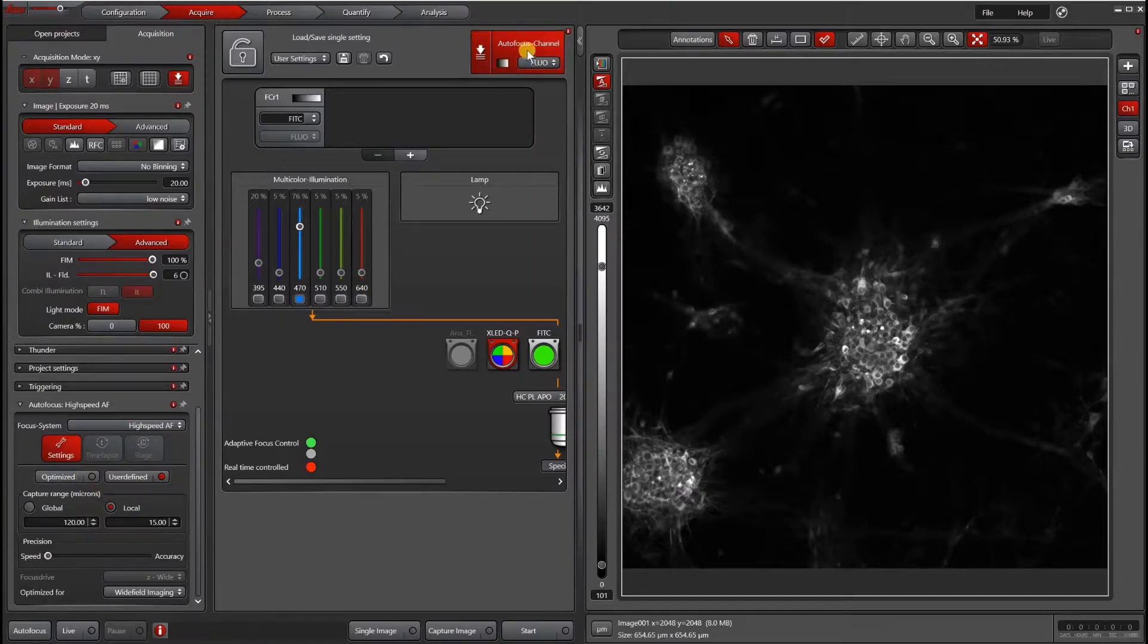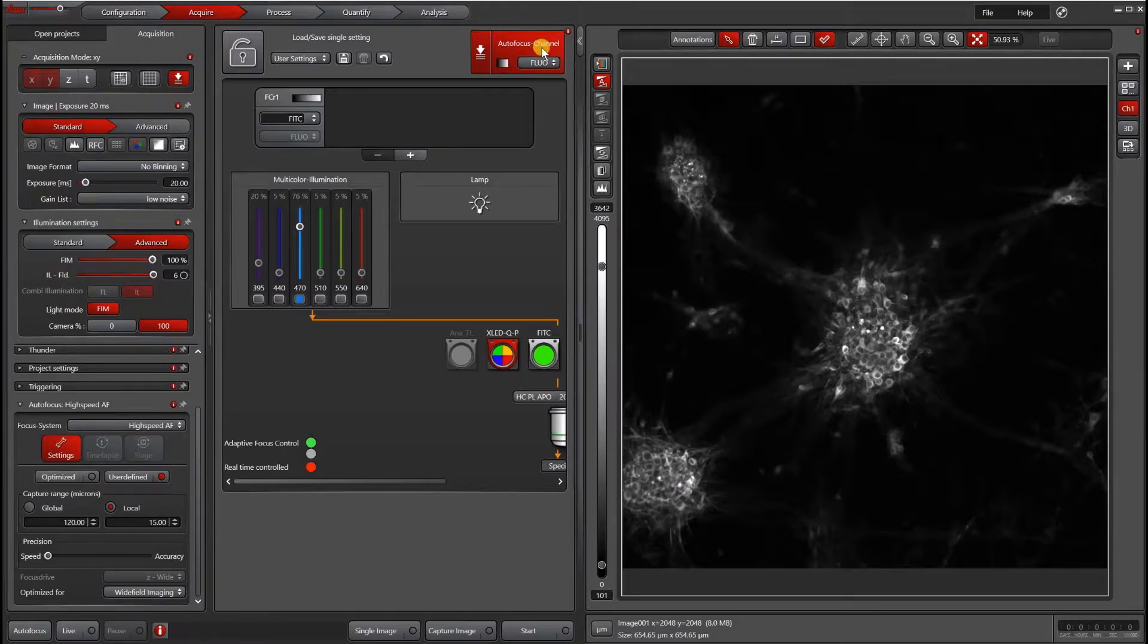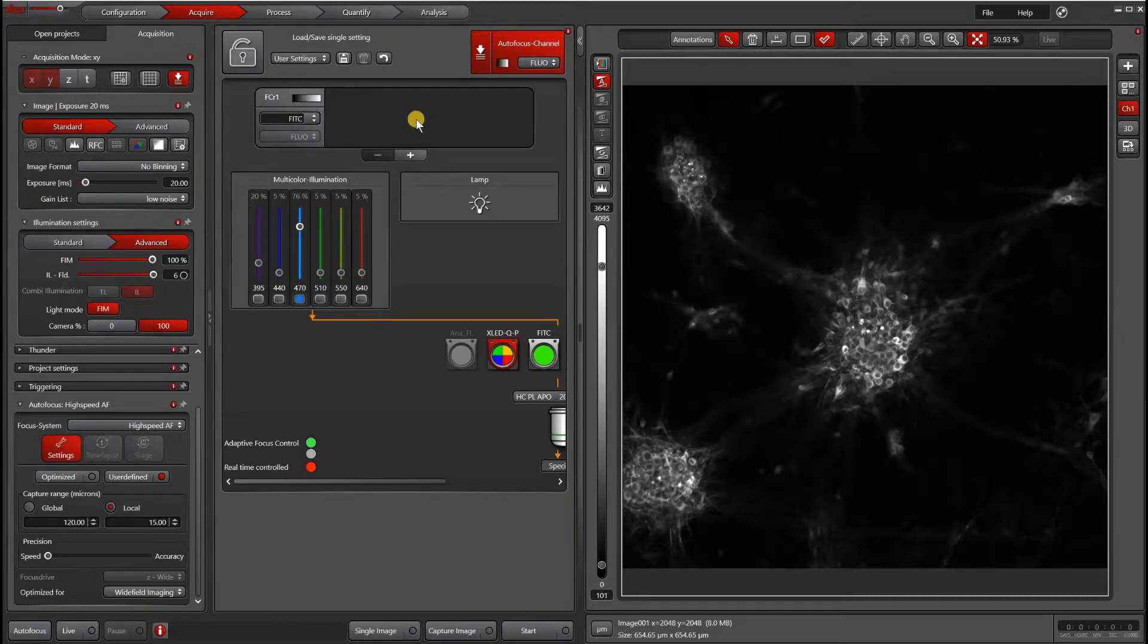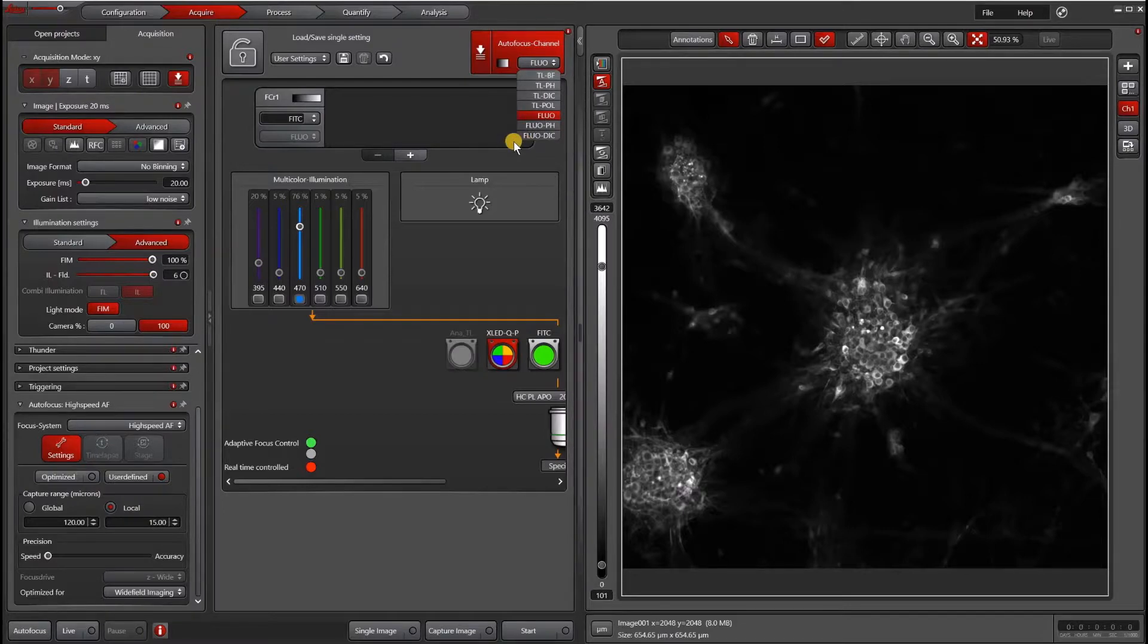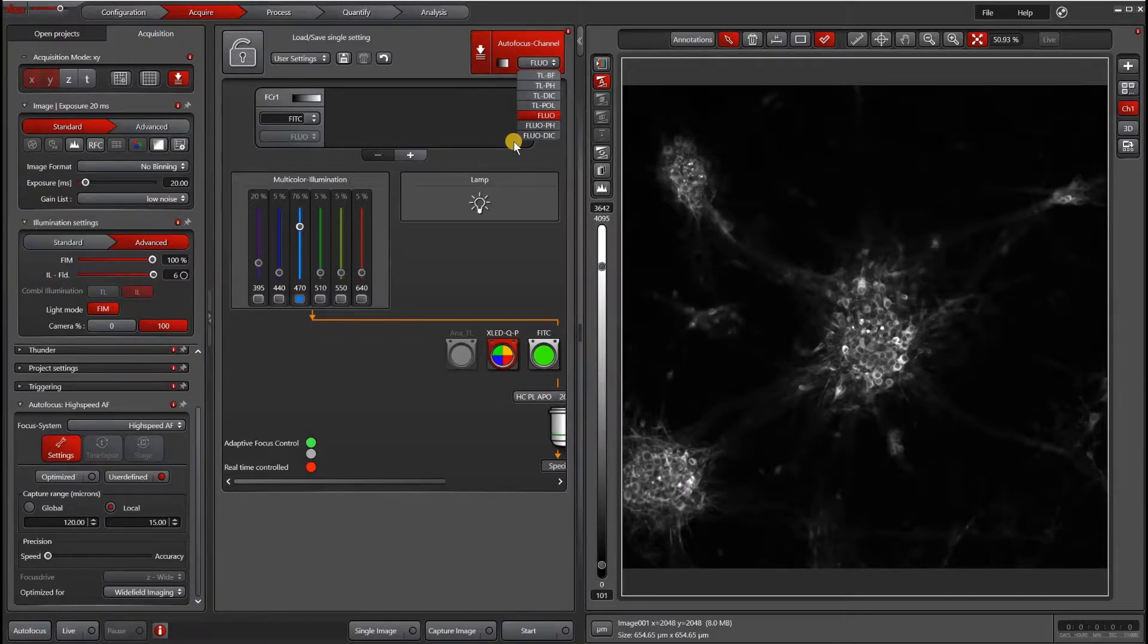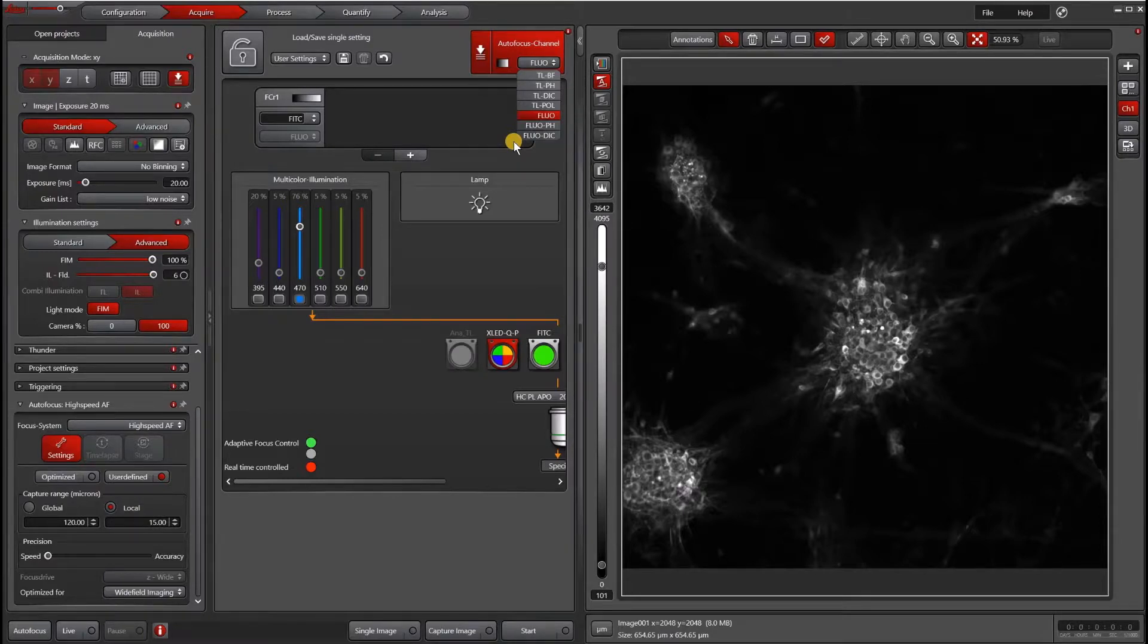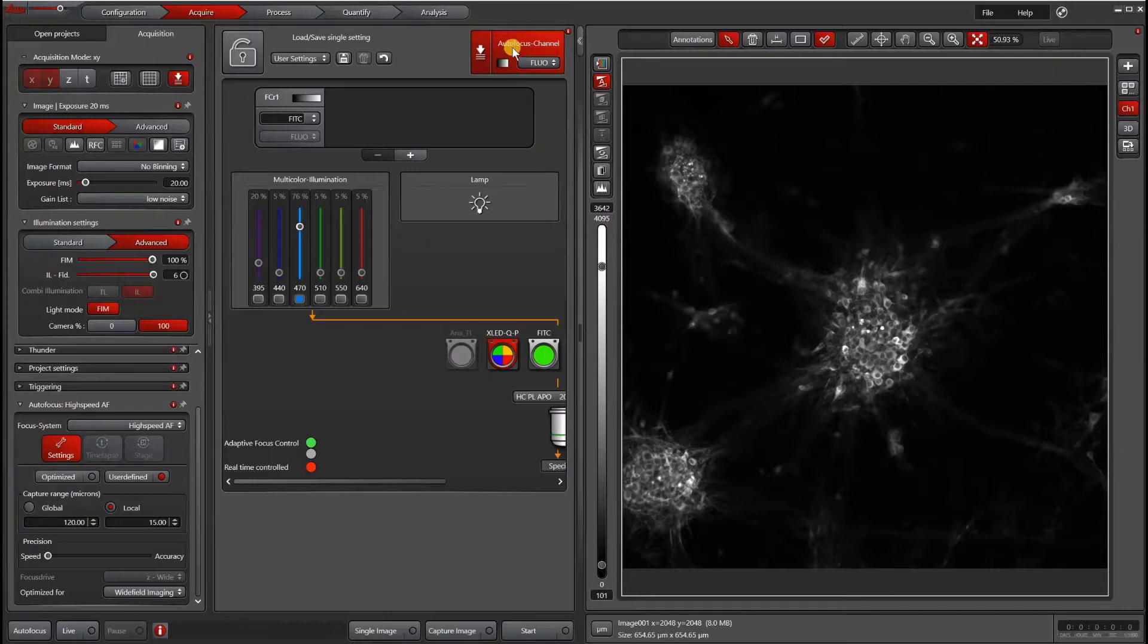So if you've selected high-speed autofocus, a channel will pop up in your light path on the top right corner, allowing you to customize your autofocus settings. If you're using best focus, you will not have this option. Most people will use the first channel in their acquisition as the autofocus channel. Under autofocus, I have the option of choosing all of my different contrast methods. Even if in the end you are using fluorescence for acquisition, you might want to choose a transmitted light, either brightfield or phase method, to do the focusing because it's usually faster and less photobleaching. But in this case, I've set it up exactly the same as my acquisition, which is in the FITC channel.